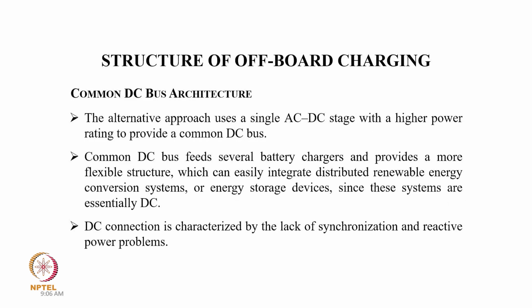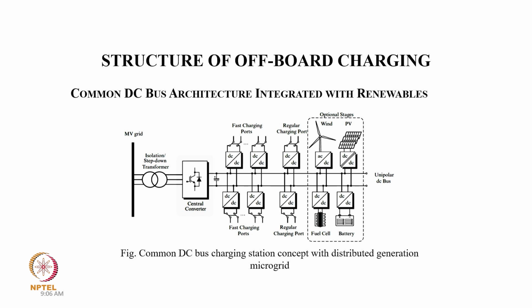Now coming to the common DC bus architecture, the alternative approach uses a single AC-DC stage with a higher power rating to provide a common DC bus. The common DC bus feeds several battery chargers and provides a more flexible structure which can easily integrate distributed renewable energy conversion systems or energy storage devices. These systems are essentially DC, and a DC connection is characterized by the lack of synchronization and reactive power problems. So this is a very interesting topology of common DC bus architecture integrated with renewables.